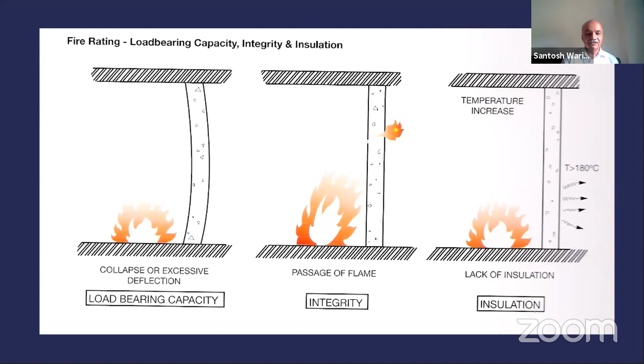Third is the insulation. If the fire is in one part, your adjacent compartment gets heated up, and if any material is stored in the adjoining compartment, that also gets ignited. So that is the insulation. These qualities are very important for any building. All passive fire protection revolves around these three principles, that is stability, integrity, and insulation. You can use different types of material, including wood, masonry, brick walls, glass, whatever it may be, but they should have these three important characteristics.